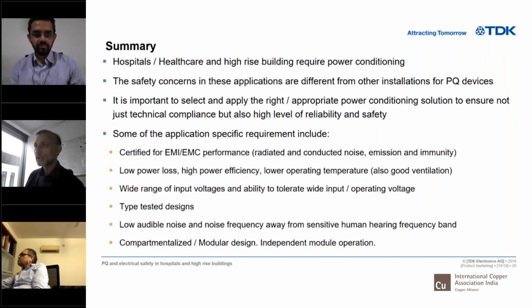So it's very critical to select and apply the right kind of power conditioning solution, not just any active filter. For lack of time, I didn't present a case study where an active filter created more problems after installation than before in a hospital. It was creating so much noise, circulating a third harmonic current, that the entire hospital's equipment was malfunctioning.